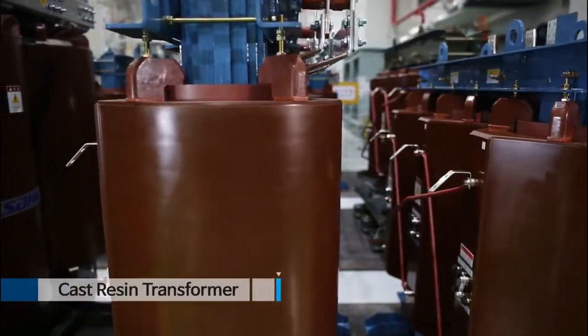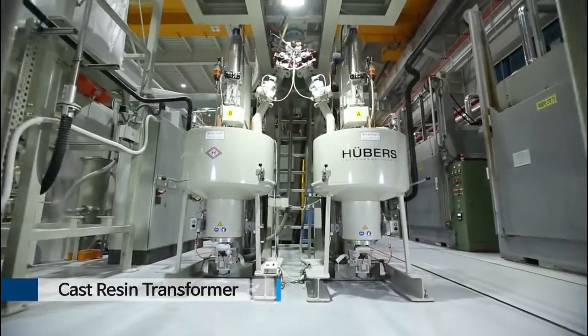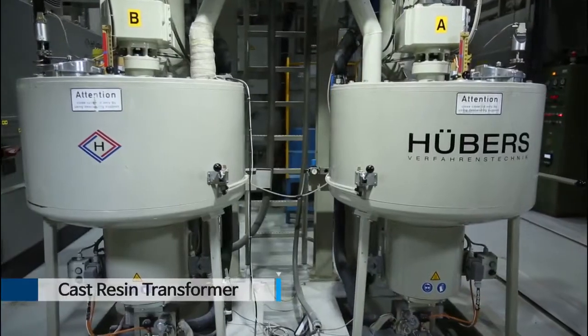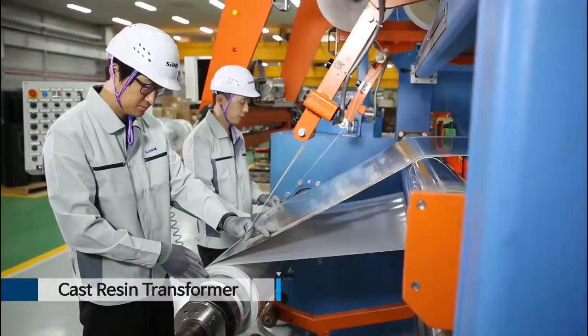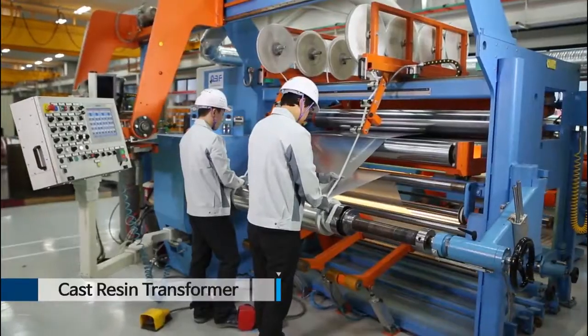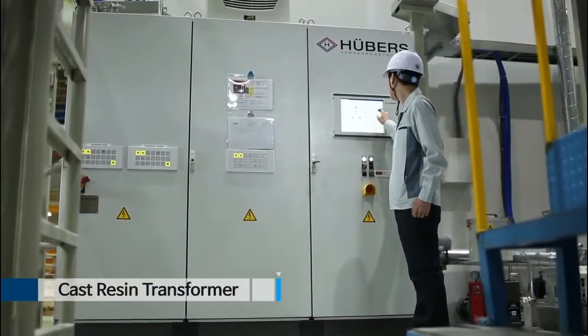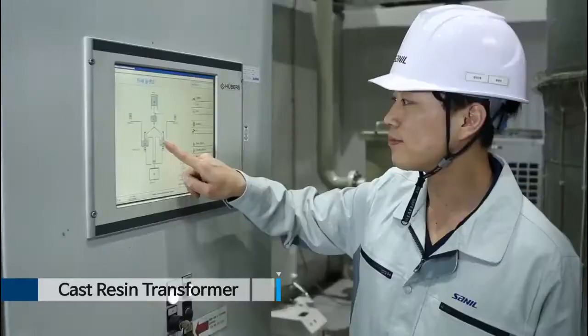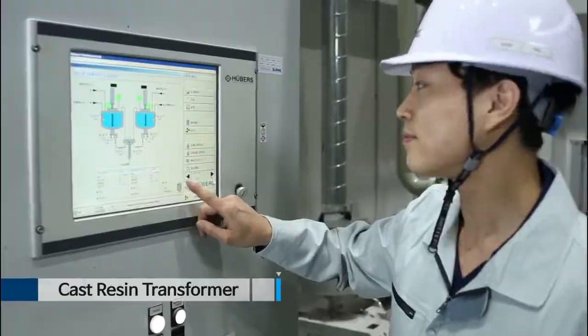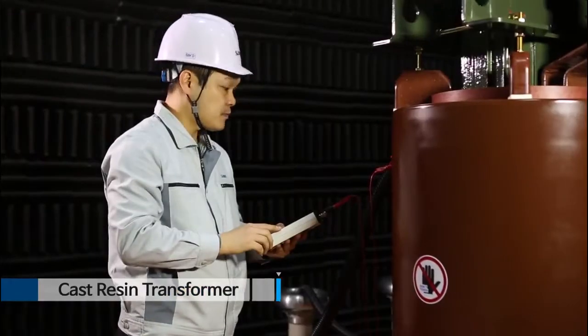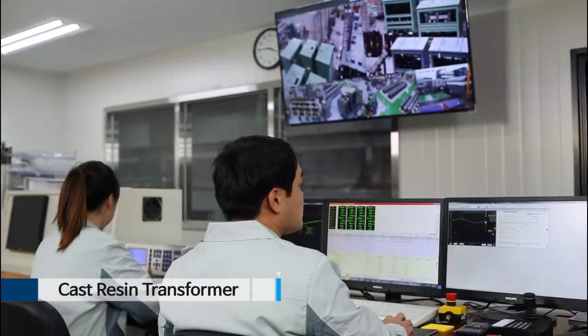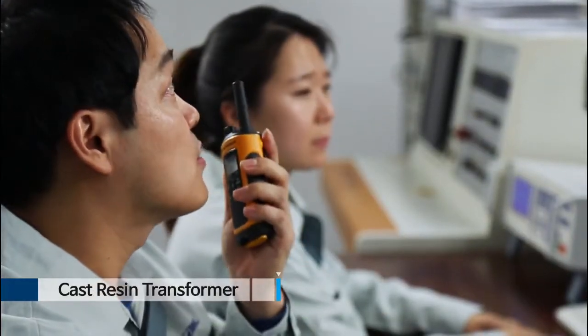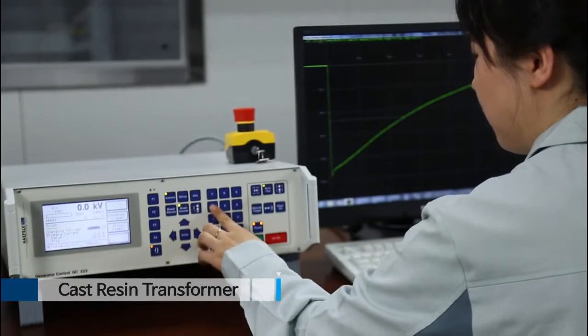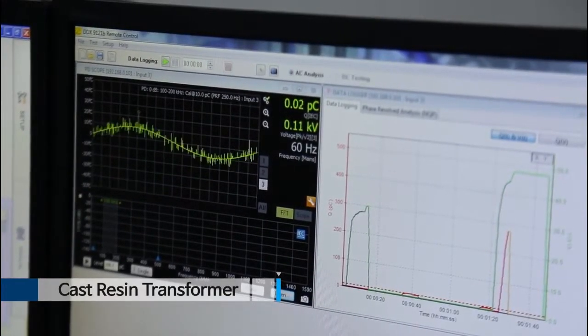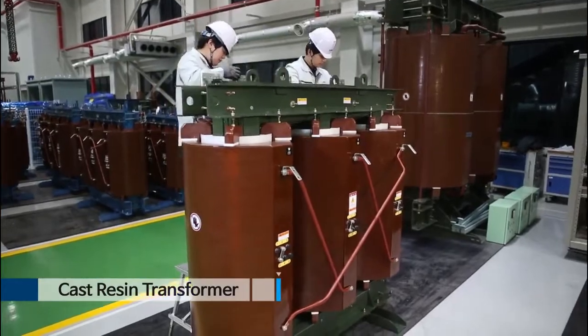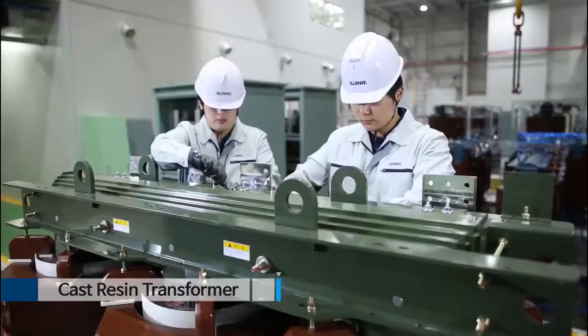Sanil's cast resin transformer is perfectly produced by using the latest vacuum molding equipment made by Hubers in Germany. Cast resin transformer winding is performed by an automated winding machine. The completed coils are dried and cast with basic materials by adjusting the vacuum and temperature. Partial discharge test is performed to meet international standards. Sanil has C2, E2, and F1 type test certificates certified by CESI in Italy. Through this, Sanil is producing the best quality products with the highest reliability that satisfy customers' needs.